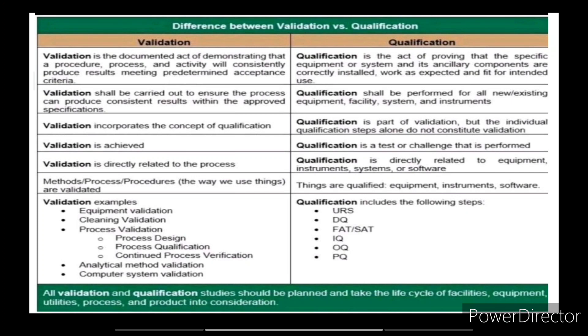Validation is achieved, whereas qualification is the test or challenge that is performed. Validation is directly related to the process, while qualification is directly related to equipment, instrument, system, or software.